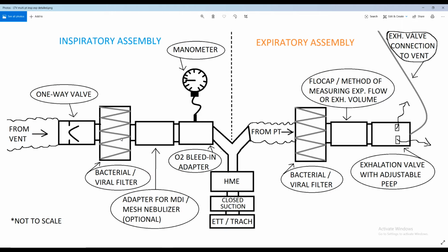So why do we want it in this particular order? If anybody's familiar with these little flapper valves that I'm talking about, this is just the one I came up with off the top of my head. Those things don't like to get wet, and they'll get sticky if they're wet, and they won't function like they should. So in an effort to keep it dry and keep that valve itself non-contaminated, we should have it go valve, then bacterial viral filter. After the filter, our patients, we've already squared away contamination and stopping patients from pushing air down their inspiratory limb into other patients. We did that with the valve and the filter.